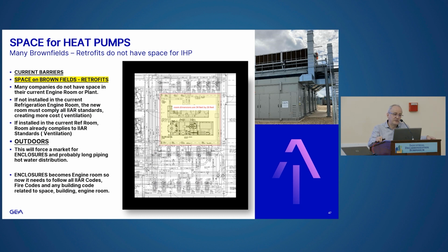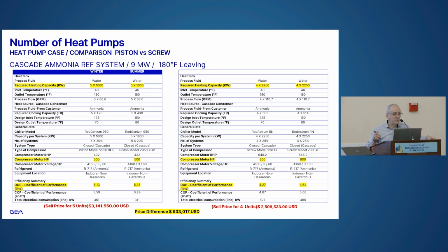Then we've seen a lot of these retrofits or brownfields, existing plants where they have limited space. They always come back with a small space to fit 1 or 2 heat pumps inside that engine room. So the market probably needs to go outdoors, but unfortunately heat pumps don't like outdoors. So you need to start thinking about making enclosures. And the last one: every time we see capacities like 9 megawatts, we have to go with 5 piston heat pumps in this case, or 4 screw heat pumps. But the customer is going to reject that because first, he doesn't have the space for that, and second, it's going to be very costly for him. So the number of heat pumps normally is going to be 3. Anything more than 3, the customer is not going to buy a heat pump.